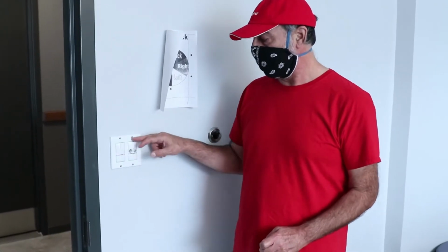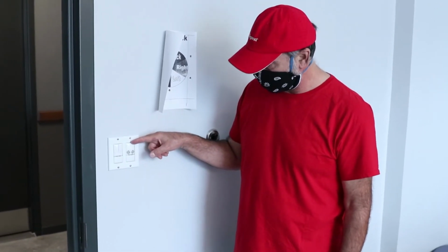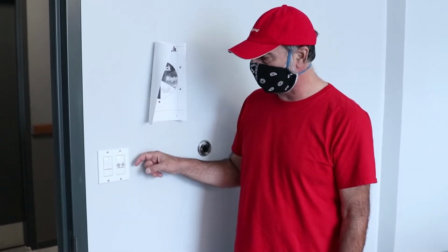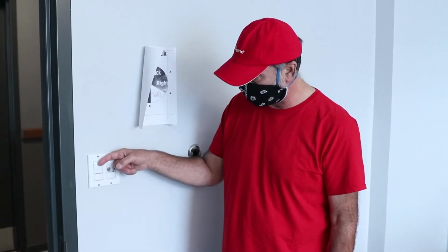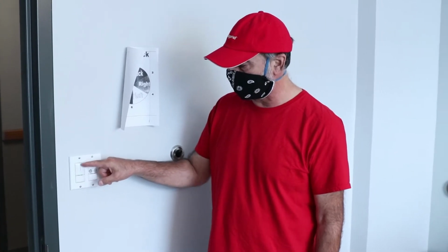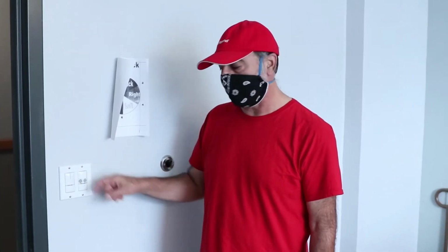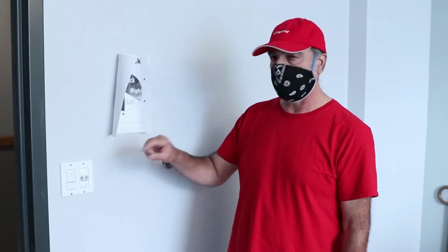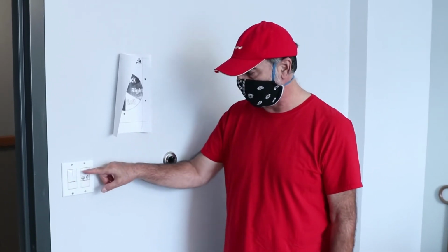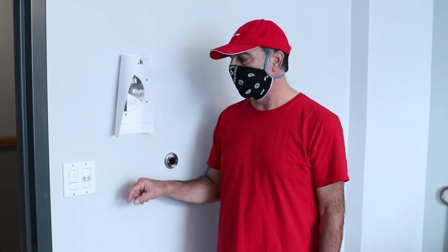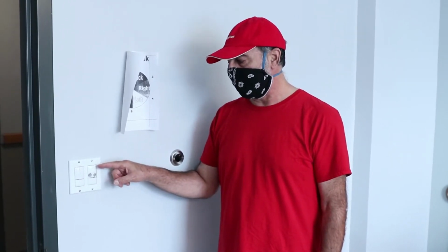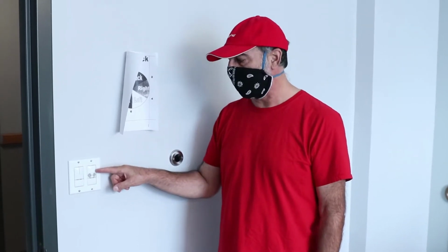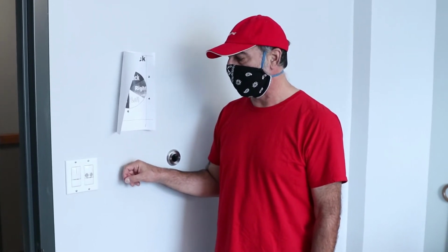That is changeable by taking this faceplate off and then prying this little cover off. In this case, prying this cover off. Even though it's split, it is attached, so carefully take this cover off. On the back of the covers and on the switch body itself are instructions, and then there's a little set of switches inside there. By setting the different switches on and off, the different patterns of switches enable you to set the timeout.